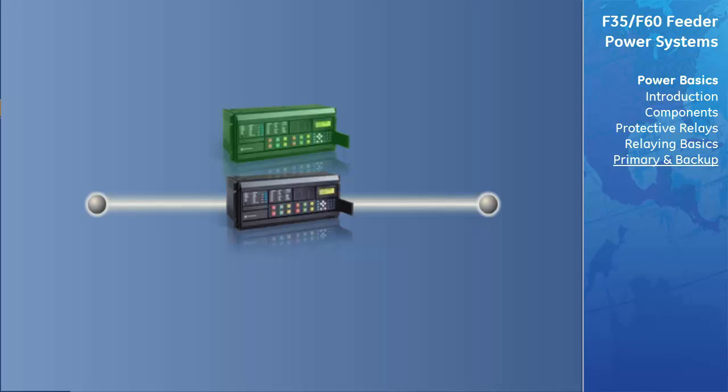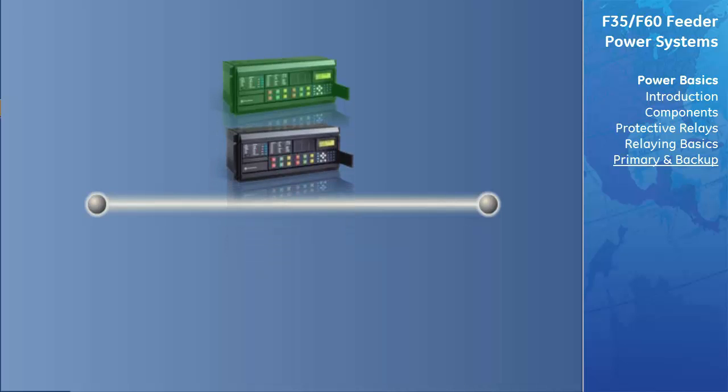Local backup protection is often used to protect against failure of both the primary relaying system and the associated circuit breaker. The only potential drawback is that local backup relaying often uses the same CTs, VTs, and circuit breakers, which can fail, likely resulting in both the primary and local backup relay also failing.